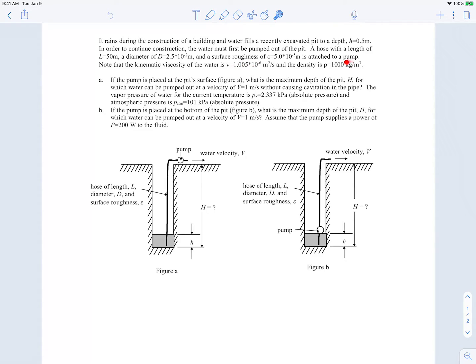Part A asks: if the pump is at the pit's free surface (top rim), what is the maximum depth H of the pit to pump water at one meter per second without causing cavitation? Cavitation occurs if pressure drops below vapor pressure. For water, vapor pressure is 2.337 kilopascals absolute, which is very small compared to atmospheric pressure of about 101 kilopascals.